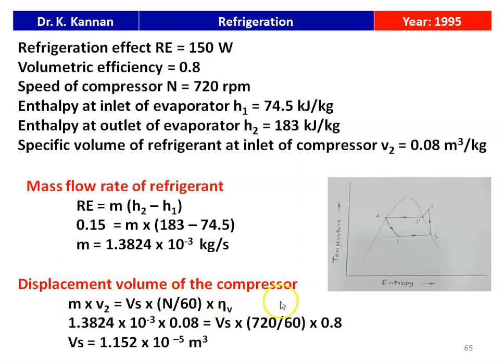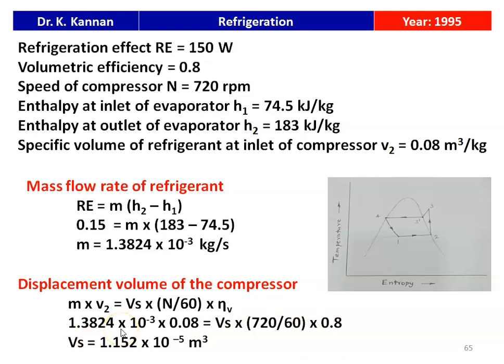The displacement volume of the compressor: volume flow rate = mass × specific volume = Vs × (n/60) × volumetric efficiency. Substituting: 1.3824 × 10⁻³ × 0.08 = Vs × (720/60) × 0.8. Calculating, the displacement volume Vs = 1.15 × 10⁻⁵ m³. This is the answer.